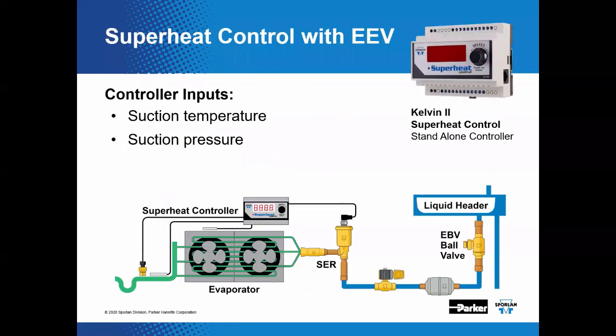Good point. Here, maybe this helps to reinforce that. When you're looking at this diagram, the inputs to this Kelvin controller in this example are pressure and actually two temperatures being inputted to this one. Yep. Jim, that question came up also about why that second sensor's on there. And for a superheat control, that sensor is absolutely not necessary. That's actually sensing, good point, the case temperature or the air temperature inside the case, so to control other features of the valve. We were just talking about a superheat control here. Sorry, we just did not get that taken out before we started this webinar.